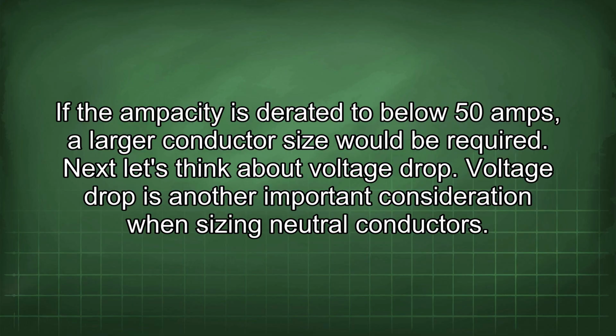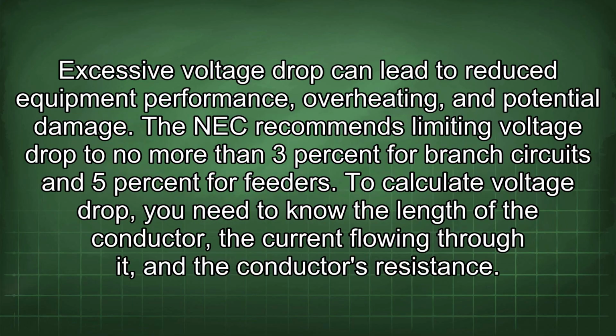Next, let's think about voltage drop. Voltage drop is another important consideration when sizing neutral conductors. Excessive voltage drop can lead to reduced equipment performance, overheating, and potential damage. The NEC recommends limiting voltage drop to no more than 3% for branch circuits and 5% for feeders.